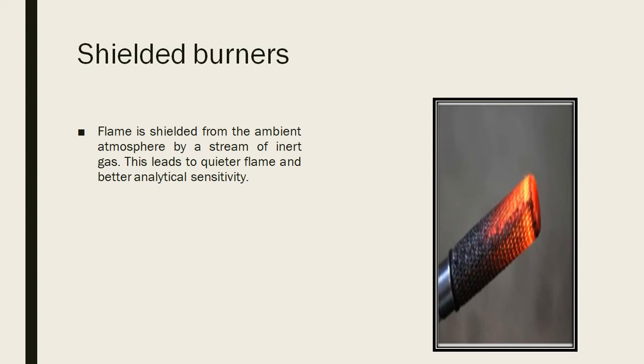Next is the shielded burner. Here the flame is shielded from the ambient atmosphere by a stream of inert gas. This will help to produce a quieter flame and it will give us better analytical sensitivity.